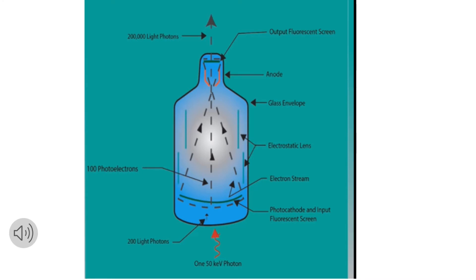Next we have these electrostatic lenses. They focus those electrons and push them to a focal point. This is where the brightness gain is taking place — this is where the money meets the road in fluoroscopy. The next part is the anode. It's accelerating, but remember, these electrons don't strike the anode. They pass by it and strike the output phosphor at the end, which produces light again.